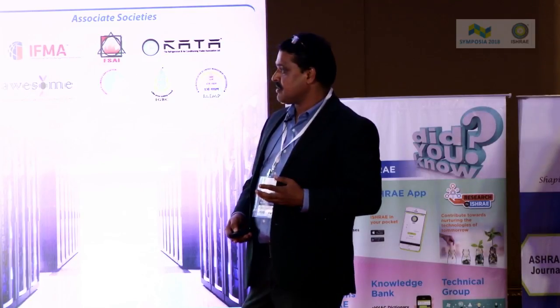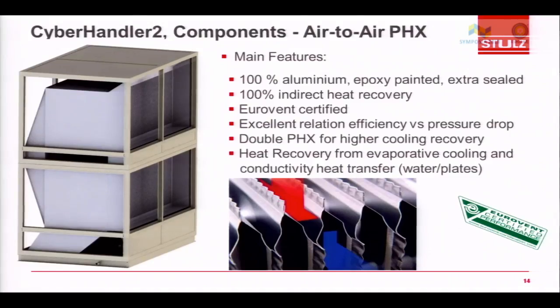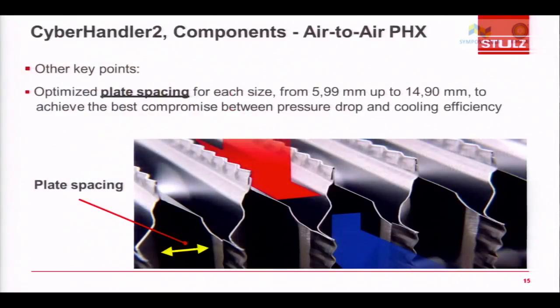Here is the game changer, which is the air to air heat exchanger, which I told you has no contact between indoor air and outdoor air. You can see hot air and cold air are not in contact with each other. The air-to-air heat exchangers are Eurovent certified. It has 100% indirect cooling. It also has evaporative cooling built into the air-to-air heat exchanger, which my next slide will cover. So you have to deploy this air-to-air heat exchanger, utilize outside energy, and ensure that the data center gets the cooling. Again, the fin spacing depends on your design, on what type of air-to-air heat exchanger you are designing.